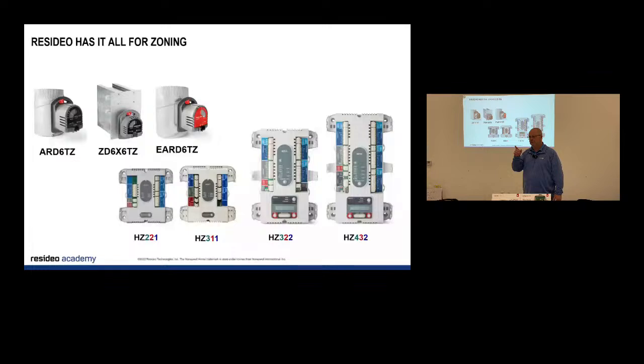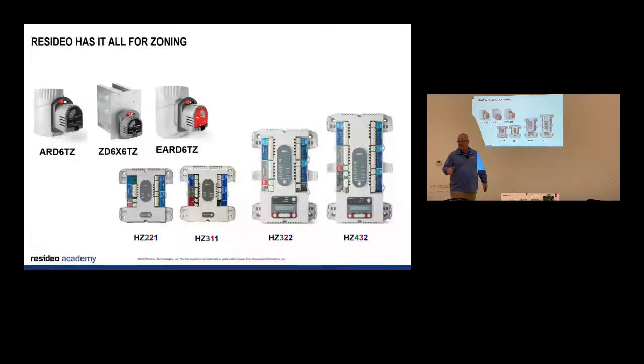So if you're generating a 3-zone, you're not gonna be dumping 60% into a master bedroom unless you've got a massive master bedroom. That's why I'm saying we need bypasses 99% of the time. Or some really big ductwork, right? And then you're gonna run wild, like you're saying. So it's a fine line between a bypass and duct design.